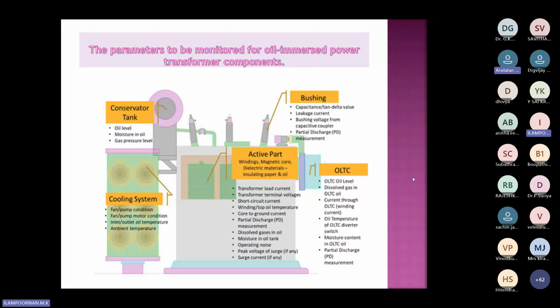Why do we need to absorb the moisture? When the oil expands, air goes out, and when it cools down and contracts, it absorbs moisture from the air. Very good. What happens when moisture enters the oil? The dielectric strength of the oil will be reduced. Only the dielectric strength of the oil? Not only that: the oil acts as a carrier and will impregnate the paper, so the dielectric strength of the paper will also reduce. So we need to prevent this inflow of moisture, and we keep silica gel.